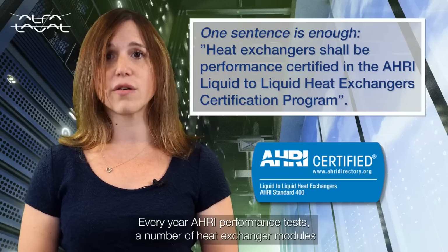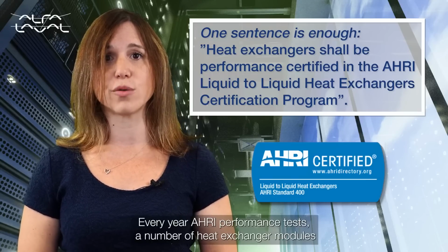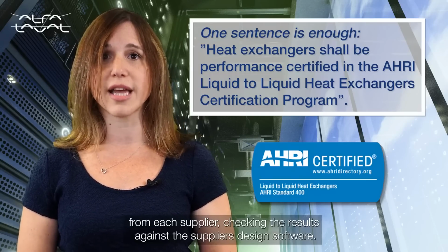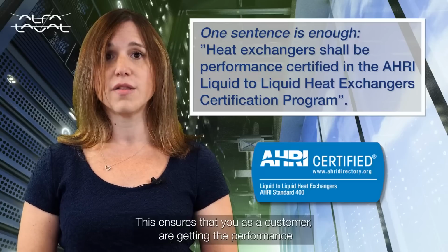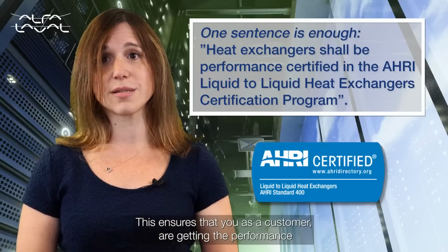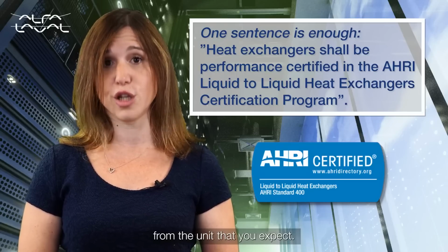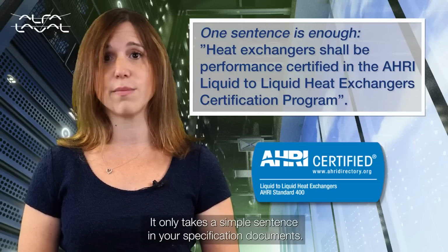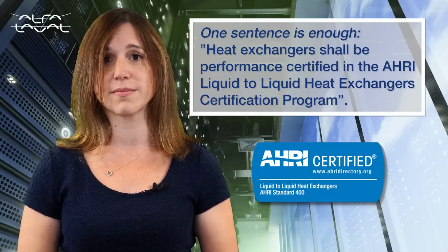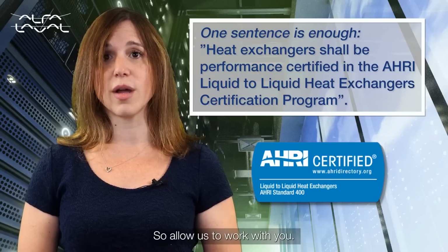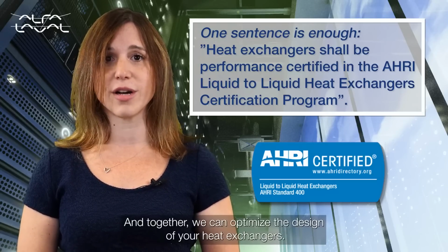Every year, AHRI Performance tests a number of heat exchanger models from each supplier, checking the results against the supplier's design software. This ensures that you, as a customer, are getting the performance from the unit that you expect. It only takes a simple sentence in your specification documents. So allow us to work with you, and together we can optimise the design of your heat exchangers.